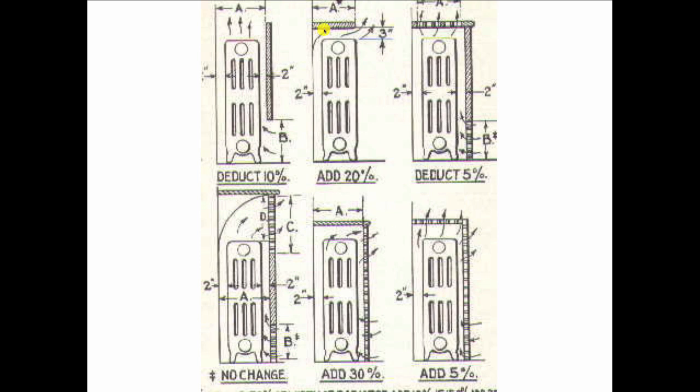So if we do something as simple as put a shelf over the top of a radiator, that stops the convective air from moving in. It bumps into the shelf. And it says here that you would have to add 20% to the size of the radiator to get the same output that you would have if that cover were not there.